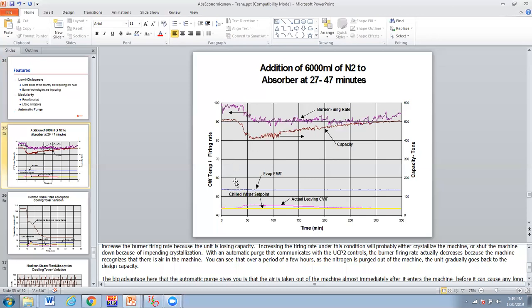Over a period of a few hours, the nitrogen is purged from the machine. The unit gradually goes back down to design capacity. So we decrease burner firing rate, and then eventually work back up to full capacity on the machine. We don't have much of an excursion in the chill water. It goes up a little bit, and so it's pretty good.